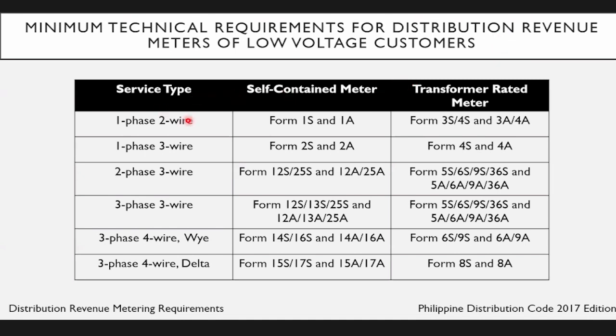If you notice, for the service type single phase two wire, the self-contained meter should be form 1S and 1A, and for the transformer rated, it should be 3S, 4S, and 3A or 4A. For the single phase three wire, the self-contained meter should be form 2S and 2A. The transformer rated meter should be form 4S and 4A.